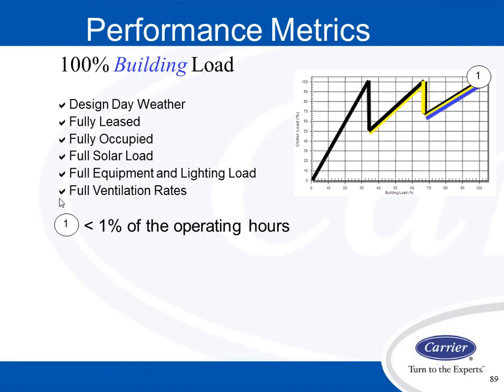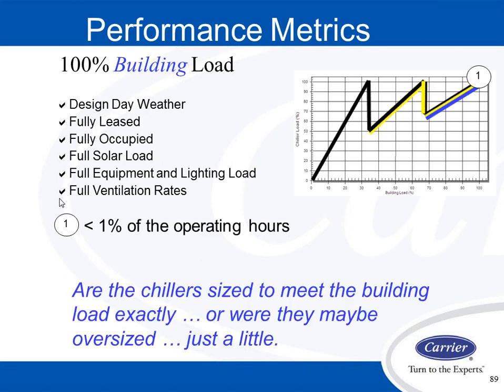So again, when we look at the performance metrics, it's basically 100% building load, design day, buildings fully leased, fully occupied, full solar load, full equipment and lighting load, and full ventilation rates. Happens less than 1% of the operating hours per year, if ever. And then, of course, all chillers are sized to meet the building load exactly, correct? No, and we all know everyone puts a little bit of safety factor when analyzing the chillers.